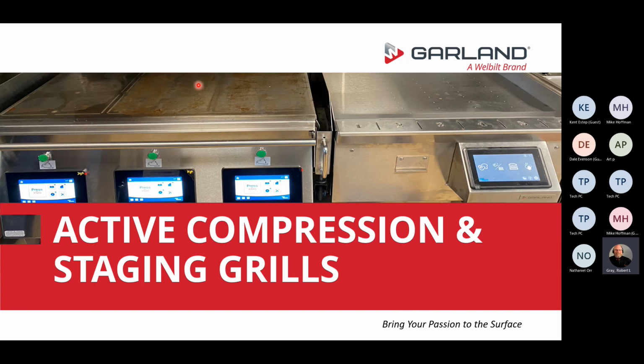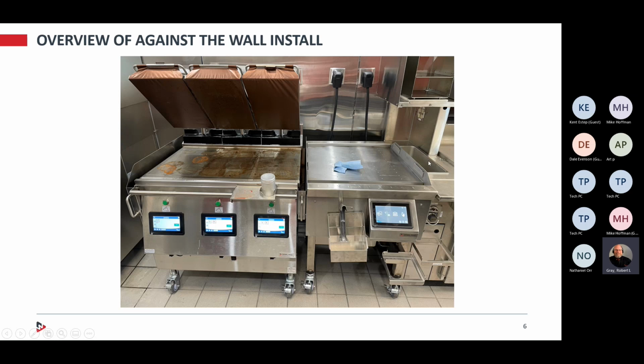But I want to point your attention to the active compression grill. You have a chicken lane and you have 2 burger lanes. You as a technician, when you're doing a startup or install or both, you have to make sure the UI is set up accordingly based off of the positioning of the grills. Let me go ahead and move to the next slide. I can show you this. If the sandwich station is over here, as you see in this picture, that means right next to that will be your staging lane grill. And then off the staging lane grill will be the clamshell grill. Now, if your prep station, your sandwich making station, is on the left side of this picture, it would mean your staging lane grill and then your clamshell grill.